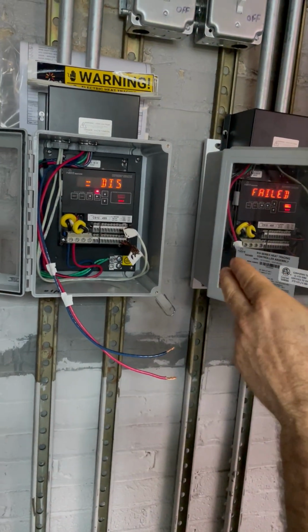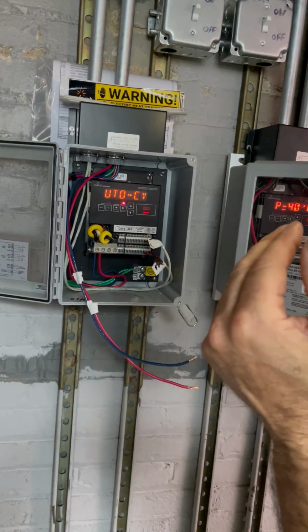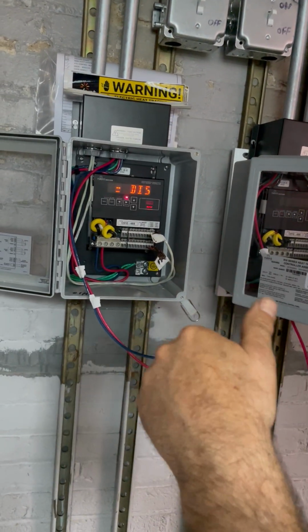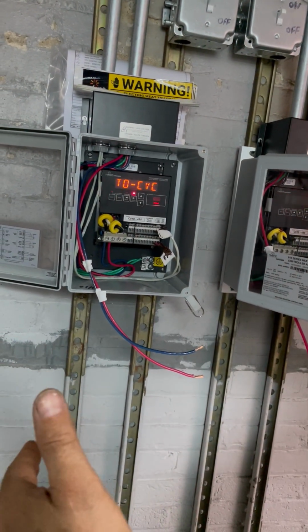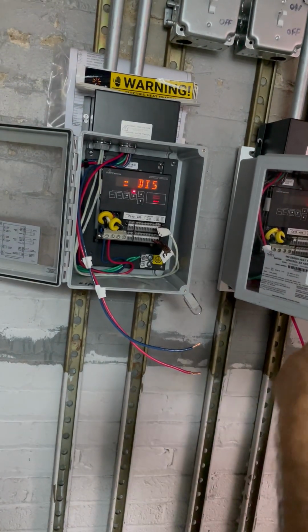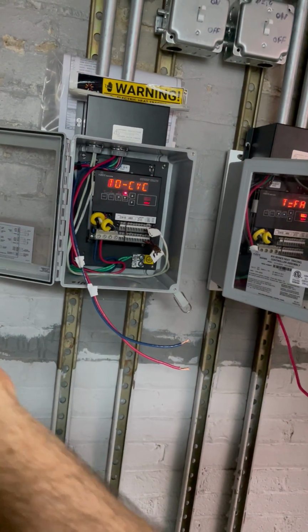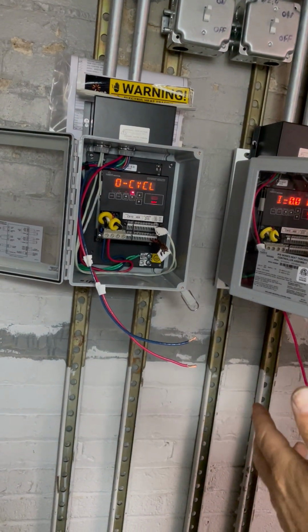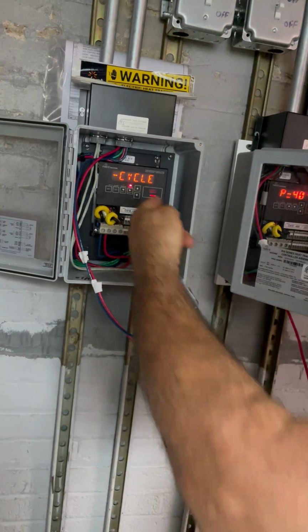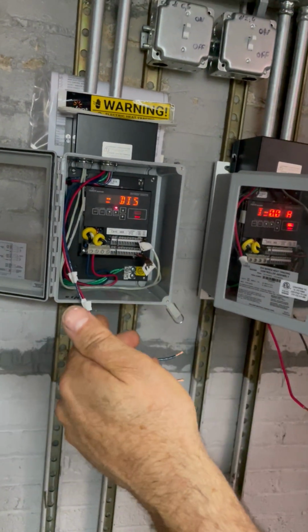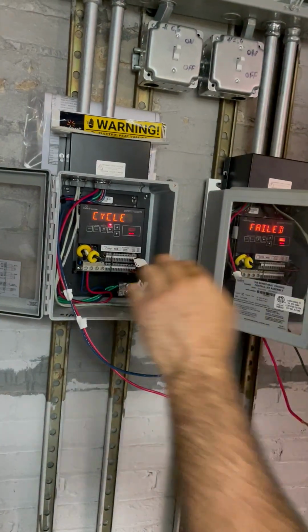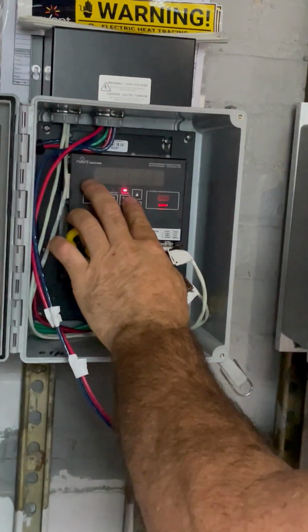Autocycle, I find this to be important. It will turn on at an interval to make sure everything is okay. So rather than waiting till it's cold in the winter, turning on, and some guy was out there changing a valve and cut the heat trace in half, you wouldn't know until it went on for the first time. With Autocycle, I'll tell it 168 hours, which is about a week. I'm going to tell it to go on.